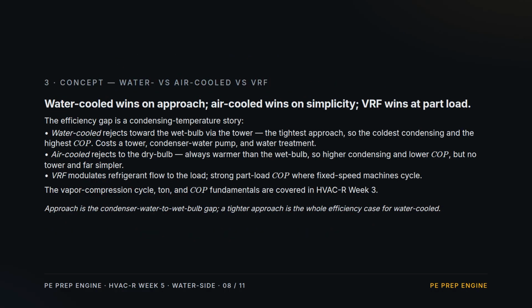Concept: comparing the 3. The efficiency gap is really a condensing temperature story. Water-cooled rejects toward the wet bulb through the tower. The tightest approach, the coldest condensing, the highest COP, but it costs you a tower, a condenser water pump, and water treatment. Air-cooled rejects to the dry bulb, which is always warmer than the wet bulb, so condensing runs higher and COP lower. In exchange, there is no tower and the system is far simpler. VRF modulates refrigerant flow to track the load, so it is strongest at part load where fixed-speed machines just cycle. The cycle, the ton, and COP fundamentals are back in week 3.